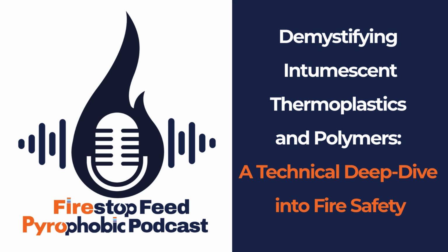An arcing fault, like a short circuit, but incredibly intense. We're talking temperatures potentially hitting 1500 degrees Celsius in milliseconds. And the scary part is many standard engineering plastics, when hit with that kind of heat, can break down and release conductive gases, carbon essentially. So the plastic itself could help the arc jump further. Precisely. One source had this vivid description, like lightning inside a volcanic eruption within the battery pack itself.